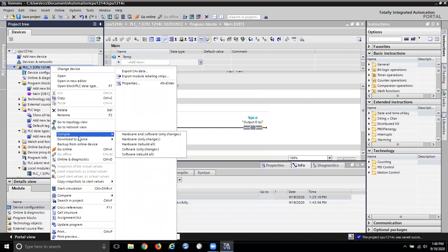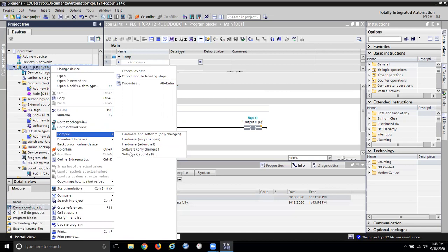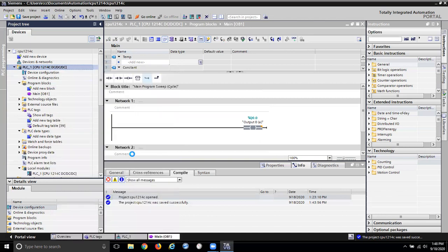If I right mouse click I should be able to compile. If it's happy with its hardware and software, you can choose hardware changes and software changes. Well, we're not changing the hardware so we could probably do software only changes, or software rebuild all. You can have it do hardware and software in case something in your hardware has changed. So let's just do software rebuild all.